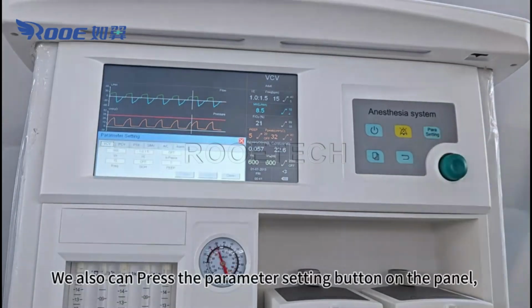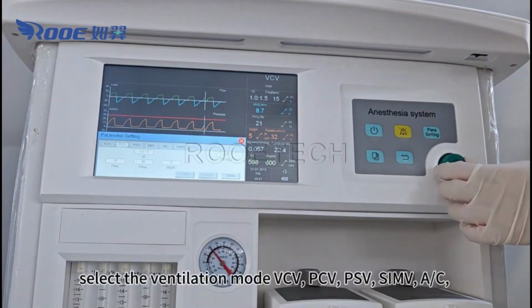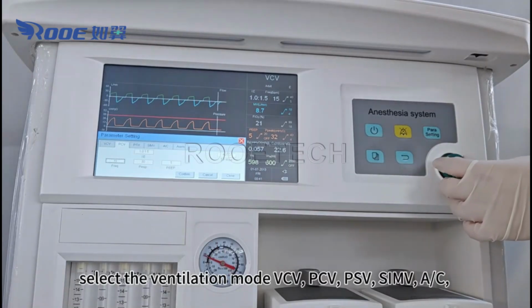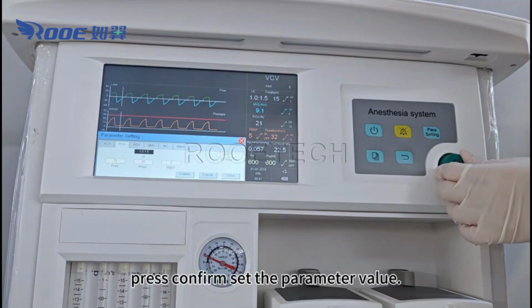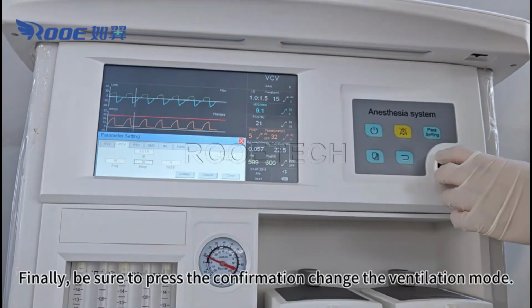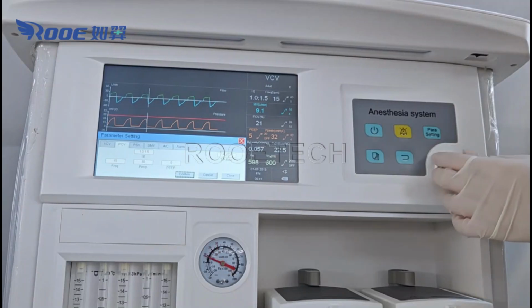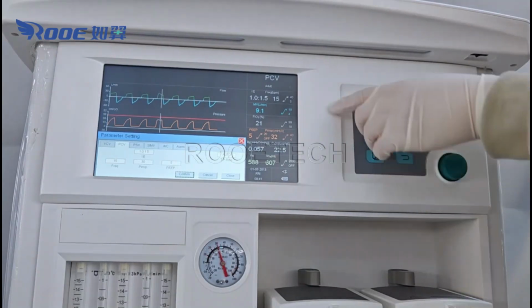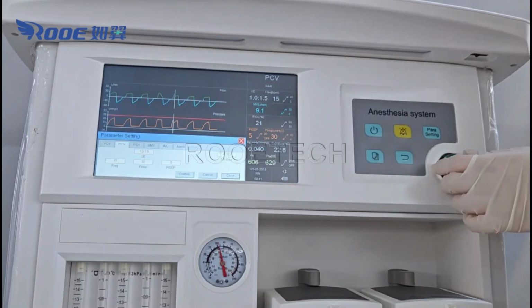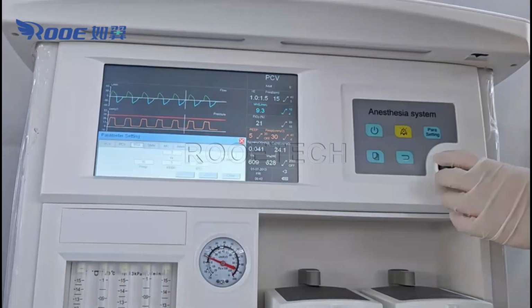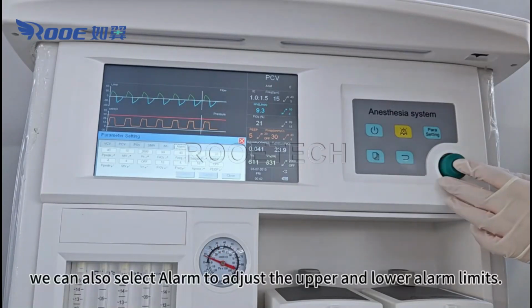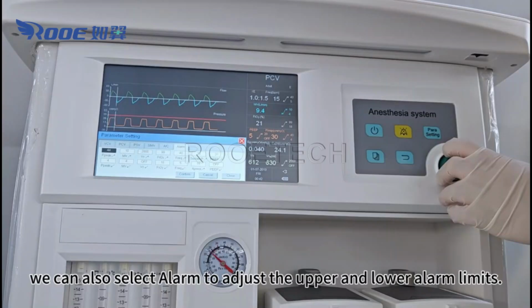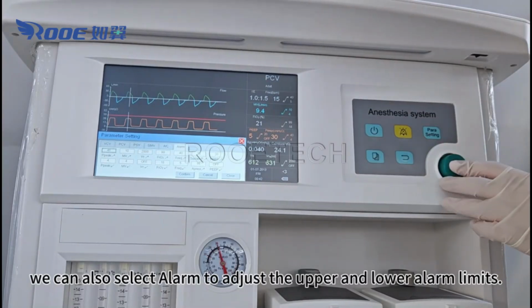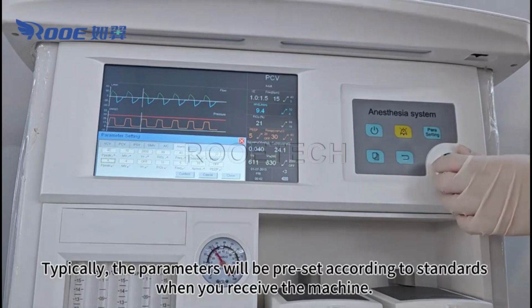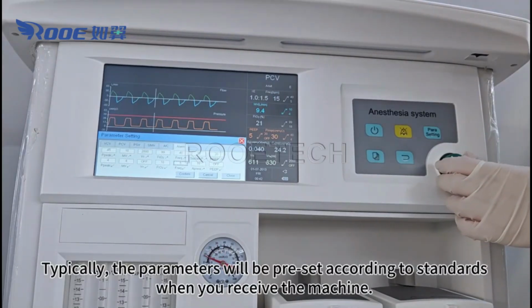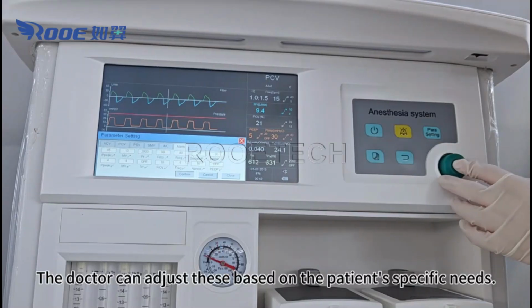We also can press the parameter setting button on the panel, select the ventilation mode VCV, PCV, PSV, SIMV, AC, press confirm, set the parameter value. Finally, be sure to press the confirmation to change the ventilation mode. In this interface, we can also select alarm to adjust the upper and lower alarm limits. Typically, the parameters will be preset according to standards when you receive the machine. The doctor can adjust these based on the patient's specific needs.